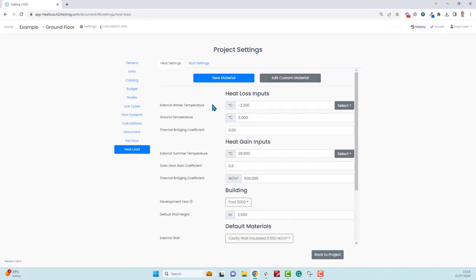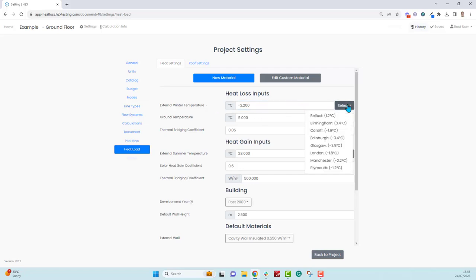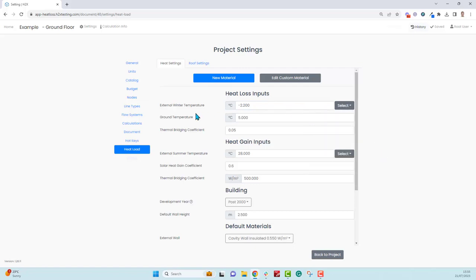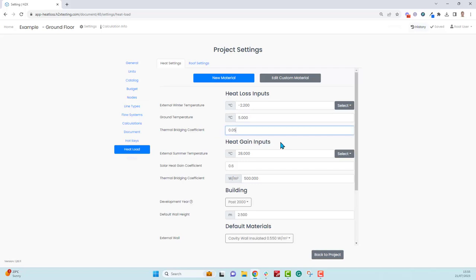Going through these one by one, the external winter temperature is used for any heat loss through external walls, windows, doors and roofs. You can enter your own number or choose from the defaults in this drop down menu. The ground temperature is used for the floor, and once again enter any number that you want. The thermal bridging coefficient is essentially a percentage that gets added on to any heat losses through the materials.